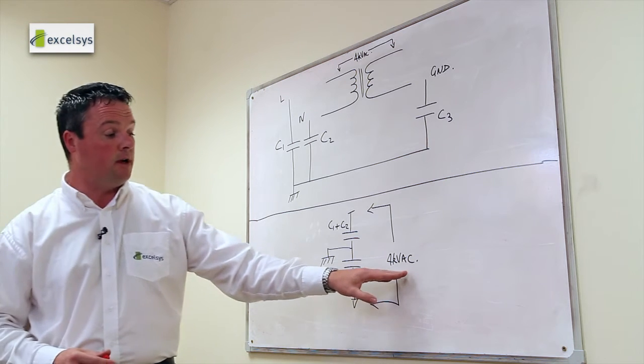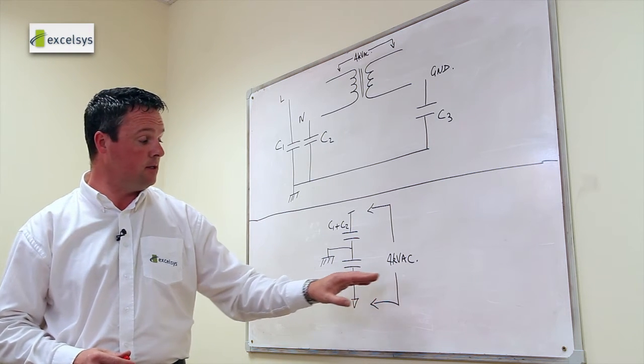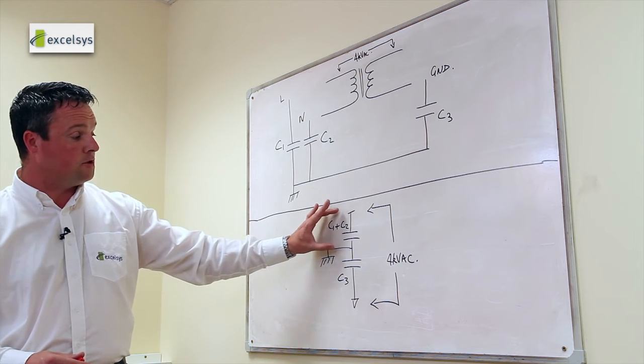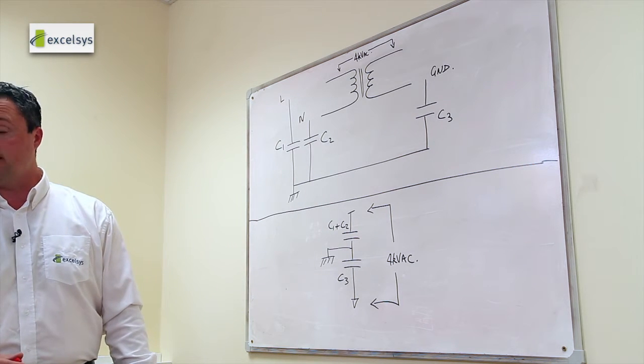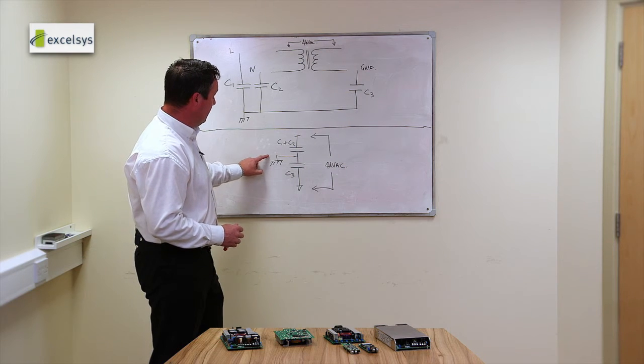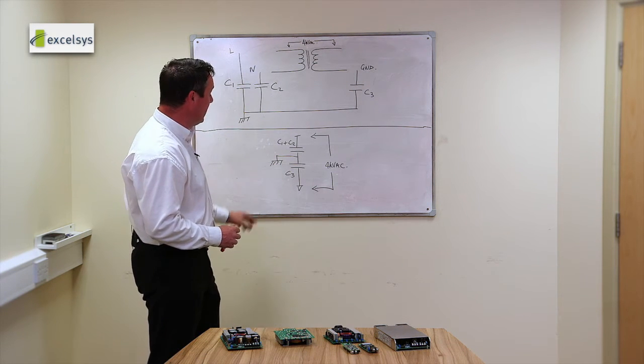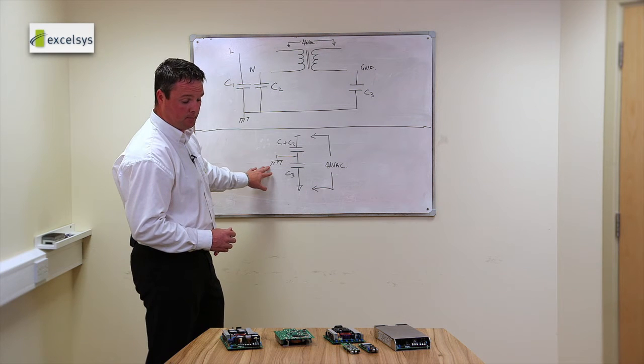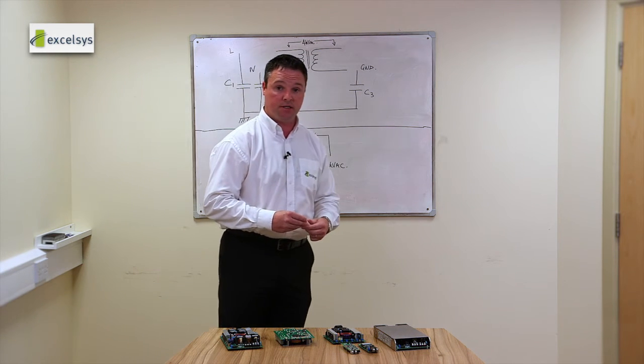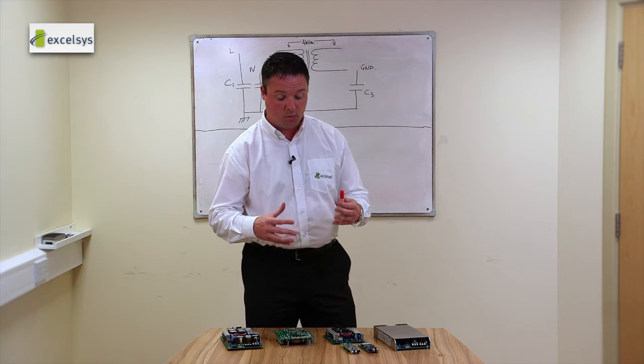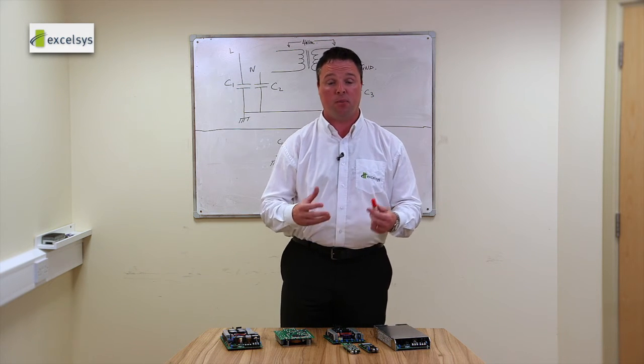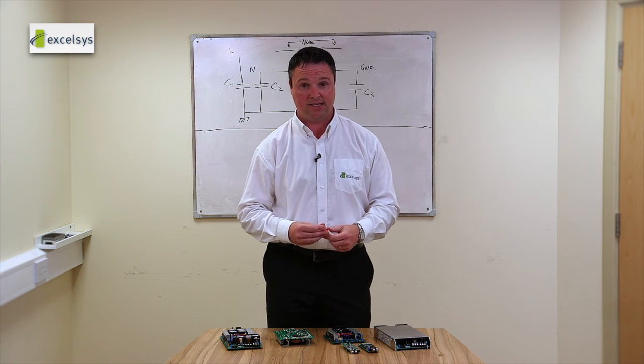And as we apply 4kV AC to these points, either the voltage across the capacitors will rise, or secondly the earth position will rise internally which may lead to arcing on the power supply. Now these of course can be designed around, but with some existing power supplies it is not possible to do a 4kV test in circuit.